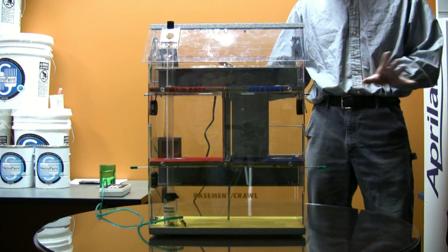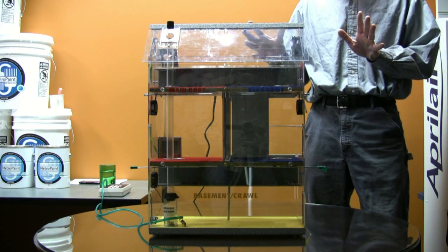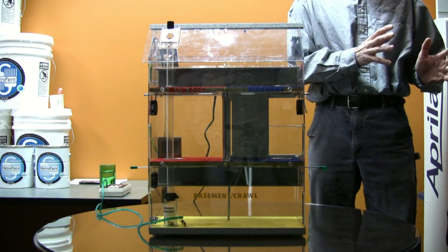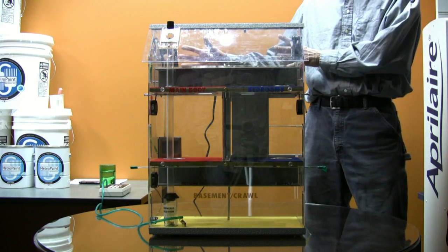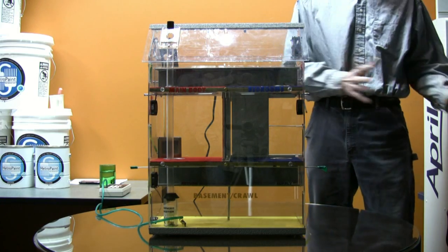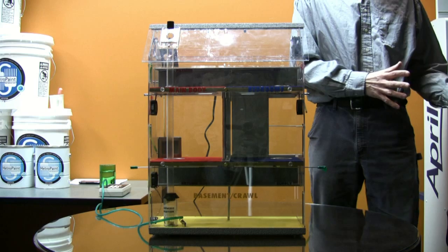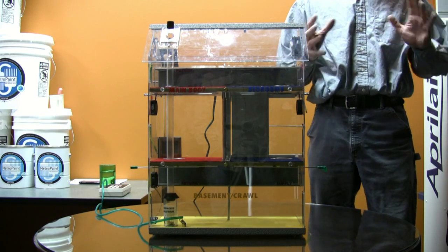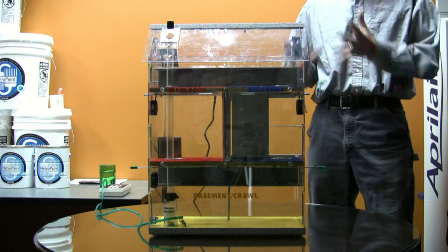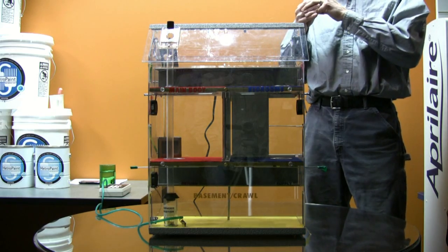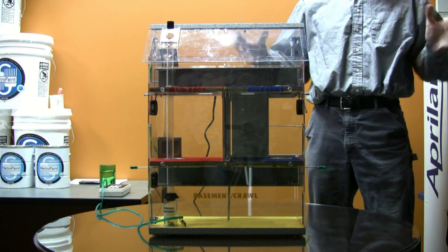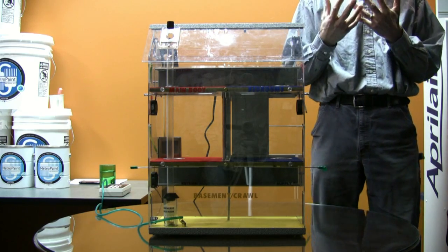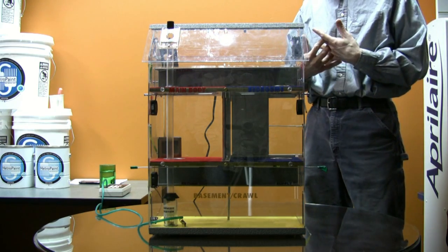Other things to learn about have a lot more to do with the ductwork, where a duct leak may cause high pressure in a certain part of the house or low pressure in another part. And that can create issues around moisture. Say, for instance, you have a bedroom with very high pressure in it, and there's a lot of moisture in that bedroom because people are breathing into it all night long. Each person gives off at least a quart of water.